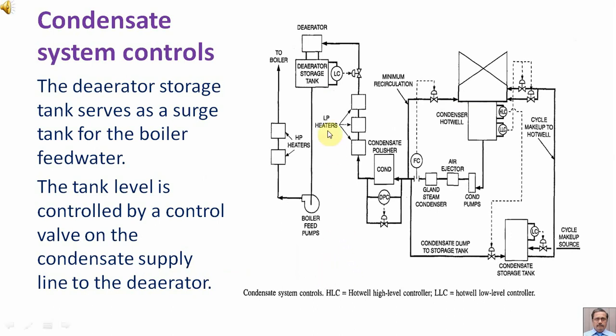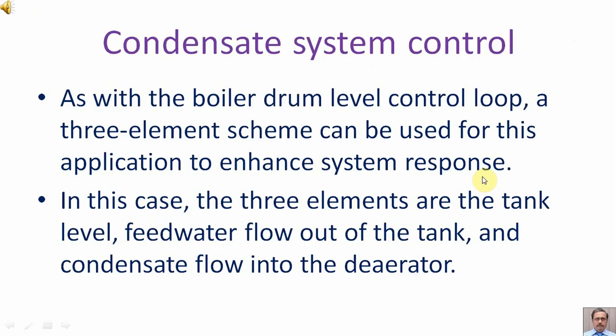The deaerator storage tank serves as a surge tank for the boiler feed water. The tank level is controlled by a control valve on the condensate supply line to the deaerator. As with the boiler drum level control loop, a three-element scheme can be used for this application to enhance system response.